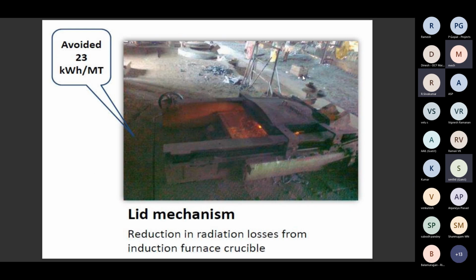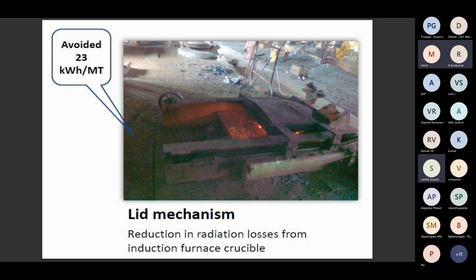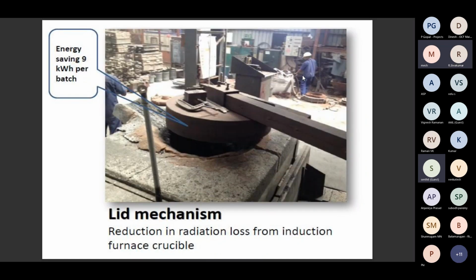So for reducing the radiation losses, this case study is also taken from the TERI reference. By using a proper lid mechanism, which was customized by the industry itself, they can avoid 23 units per ton because of this lid mechanism. So the radiation losses are reduced. Next one. In this foundry, 9 units per ton was reduced due to this lid mechanism. Next.